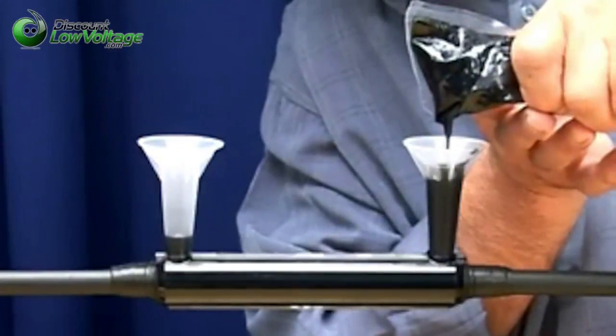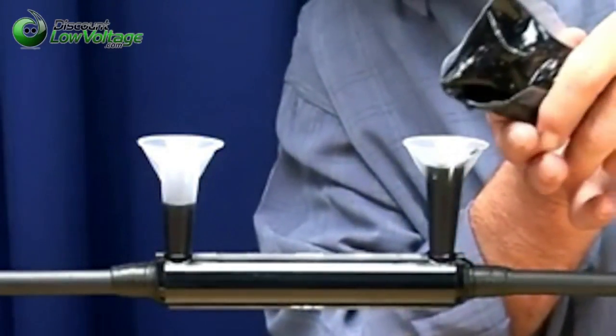Splice cure time is 1.5 hours and is submersible in 4 hours. Clip off the spouts if desired. Your 82A1 power cable splice is now complete.